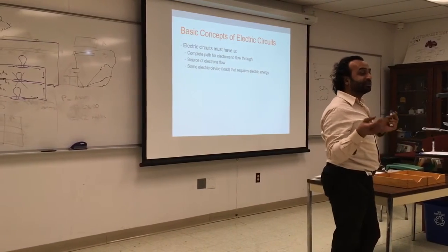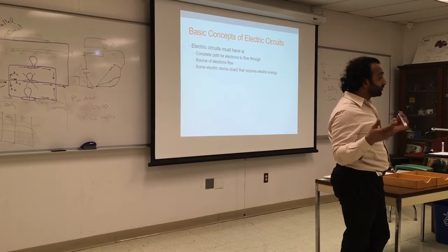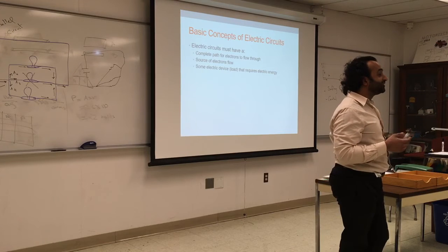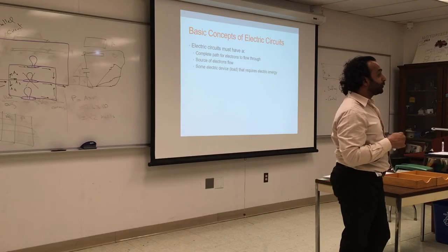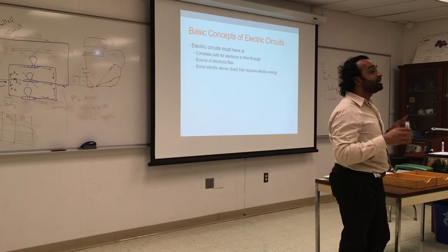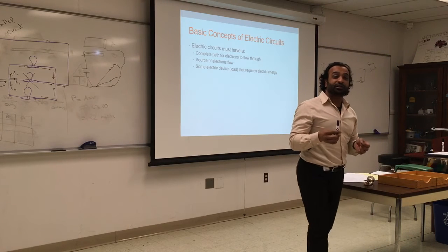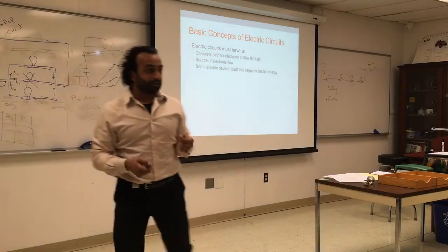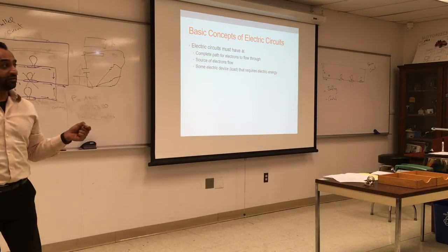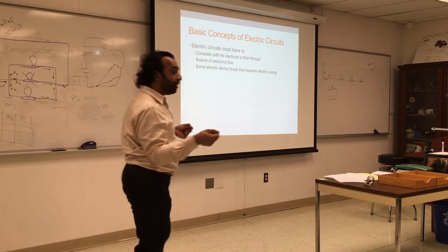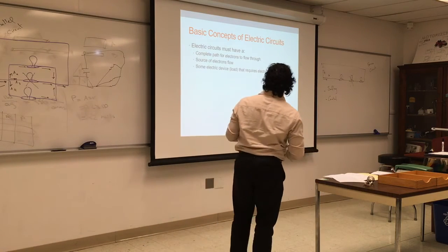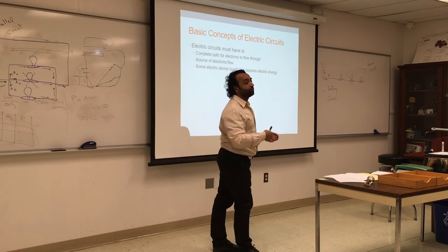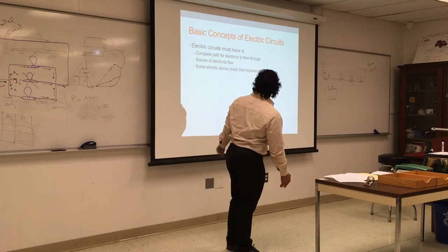You go and something is loose and the whole thing is getting power. It gets frustrating. Big circuit, and probably there's a loose nut somewhere, and it's very frustrating to find out where the incomplete circuit is. That's when you need your best friend, the multimeter, to check point by point, like from the beginning, and check the continuity of every component while it's off. Make sure you have a continuous circuit. It gets difficult when you have controls, so you also have to check the power at each terminal.